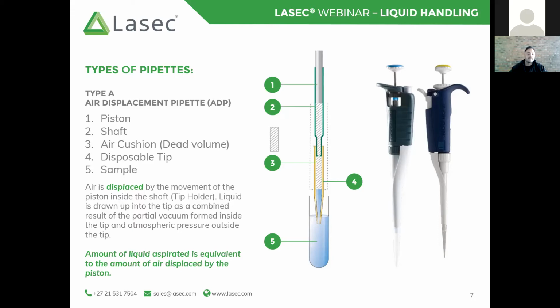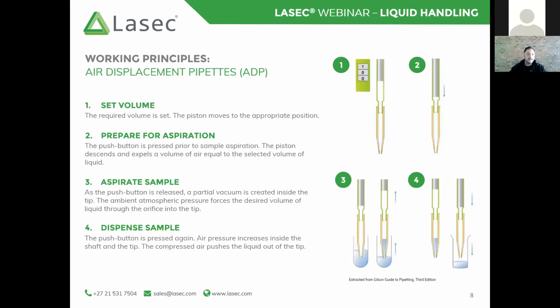And with an air displacement pipette, an important characteristic is that there's always an air cushion between the sample and the pipette itself and the piston. So that basically means that there's always a dead volume of air. Essentially, as you depress that piston, it displaces a certain amount of air. As you release the push button, that piston is going to return to its rest position or its set position, thereby causing a partial vacuum inside of that tip that's going to be lower than the atmospheric pressure outside the tip. This forces liquid into the tip, and it is extremely important that we maintain that vacuum. All right, so I hope that sums up how an air displacement pipette works.